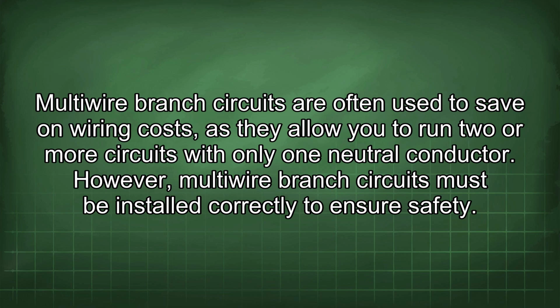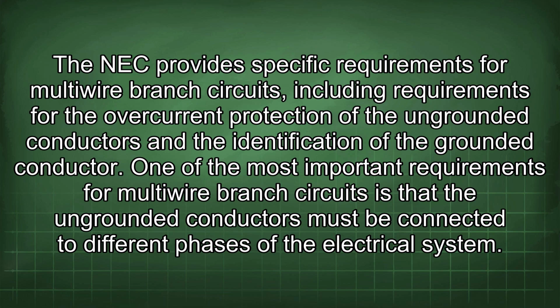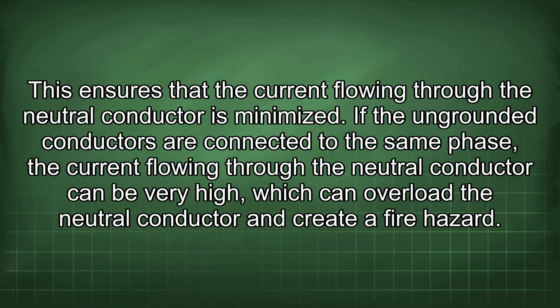However, multi-wire branch circuits must be installed correctly to ensure safety. The NEC provides specific requirements for multi-wire branch circuits, including requirements for the overcurrent protection of the ungrounded conductors and the identification of the grounded conductor. One of the most important requirements is that the ungrounded conductors must be connected to different phases of the electrical system. This ensures that the current flowing through the neutral conductor is minimized. If the ungrounded conductors are connected to the same phase, the current flowing through the neutral conductor can be very high, which can overload the neutral conductor and create a fire hazard.